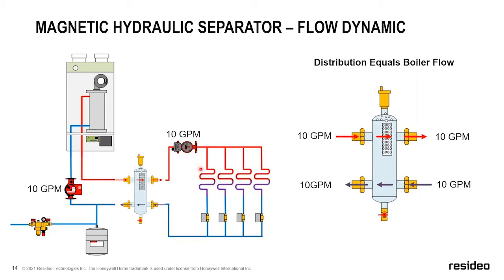But what will happen is a lot of times in modern systems, you're going to see varying flow rates on the system side. So you're going to have a pump here that is dedicated to driving adequate flow through this heat exchanger on the maximum fire. And then out here on the system, as we've gone to variable speed pumps, you'll see this flow rate fluctuate dramatically. And I'll get into that.